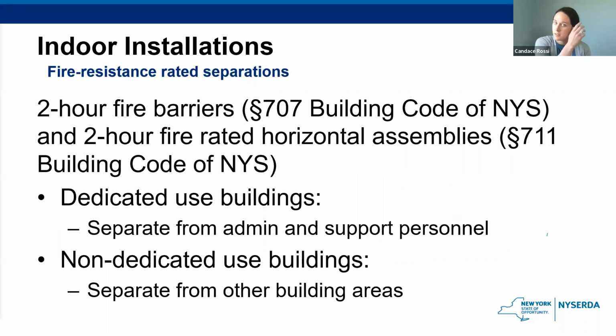And then the last additional requirement that indoor installations have to meet is the fire resistant rated separations. So 2-hour fire barriers are needed in a room or area for indoor installations. Basically, for dedicated use buildings, this must be put in place to separate from admin and support personnel. And for non-dedicated use buildings, it's basically any room separate from the other building areas. So the majority of it will have to be rated with this fire resistance.